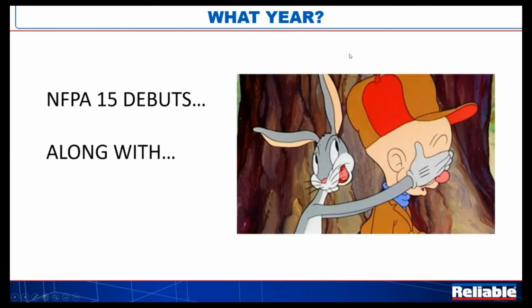Now, in a building, obviously, most often we have passive protection, either in the form of some sort of wrapping with a non-combustible material or some sort of spray-on type Monokote affair. We don't typically see water spray systems used to protect building structure, although, in the case of upright sprinklers, we do get some benefit of steel protection or wood protection in that case. So as far as structure goes, not necessarily for the building structure, more for the supports of these various type of assets. So let's play a little question of what year did NFPA 15 debut, along with Mr.